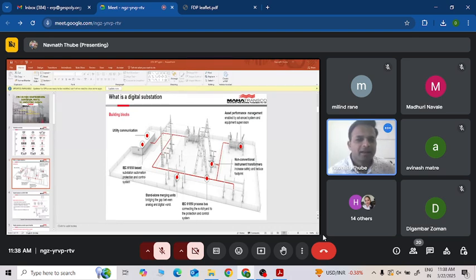This is a conventional type relay wiring. It requires a lot of wiring from CT, PT, transformer internal side, WTI, OTI, with complicated wiring, which is difficult to connect and difficult to troubleshoot. It is also difficult to replace the relay. However, in a digital substation, just two to three fiber optic wires come from the switchyard, making wiring connection easy. It is also very easy to find or rectify issues in operation.